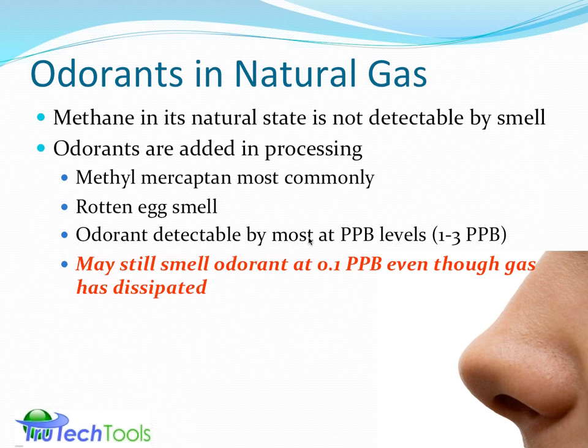So the odorants are chemicals that are added to the natural gas in the processing, in the delivery process. It's usually methyl mercaptan. It produces a kind of sulfury smell, or smell like rotten eggs, which can be detectable at very, very low levels. However, kind of the rub here is the odorant can still be detected at 0.1 part per billion, which is a thousandth of a part per million. Even though the gas is dissipated, the odorant may still be detectable.